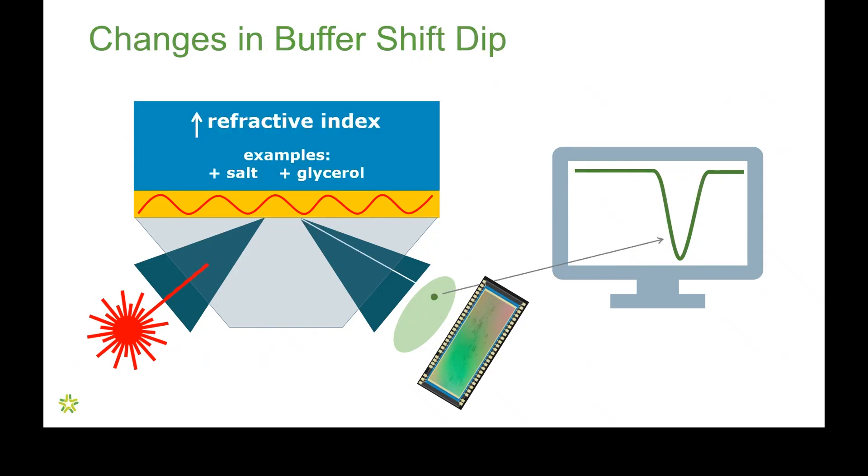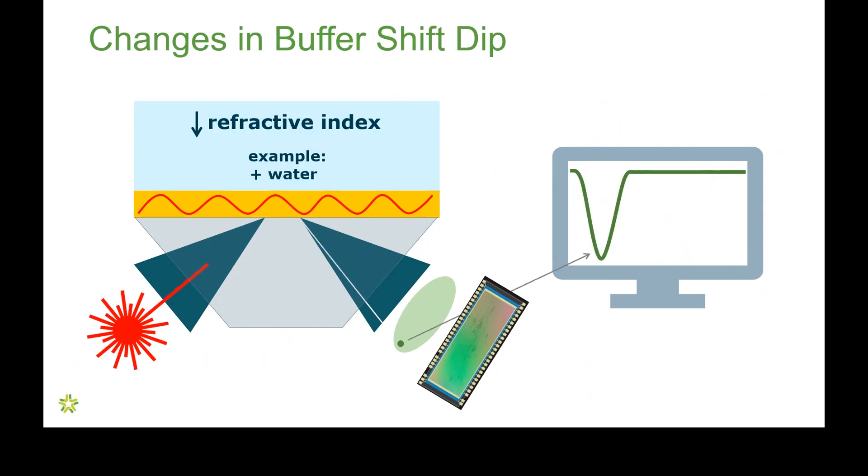So, that dip can shift to higher angles or to the right when we increase the refractive index of the buffer. Ways to do that are adding salt to the buffer or adding glycerol. Both of those increase the refractive index of the buffer. We can also decrease the refractive index by diluting buffer. Diluting it with water, for example, shifts the dips significantly to a lower angle or to the left on this screen.